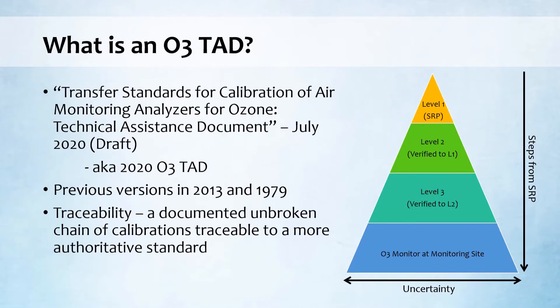What is an Ozone TAD? The full name is Transfer Standards for Calibration of Air Monitoring Analyzers for Ozone Technical Assistance Document. The current draft version came out in July of 2020, and EPA solicited comments and feedback up until May of 2021. This 2020 version will replace the previous 2013 version, which replaced a 1979 version. The 2020 Ozone TAD and its predecessors describe the process of ozone traceability, defined as a documented, unbroken chain of calibrations traceable to a more authoritative standard. The Level 1 Standard Reference Photometer is your highest authority, and that authority is passed from standard to standard until you get to the instrument that actually measures ambient ozone data at the monitoring site.